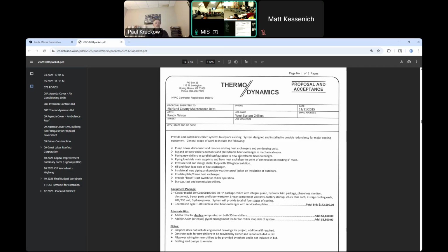We bid this basically also with all weld pipe from chillers to our manifold and into the plate exchanger. Your 4-inch existing loop would pipe right into the other side of this plate frame heat exchanger. It's included in the bid as well, along with the insulating and so on, the way the proposal spells it out.